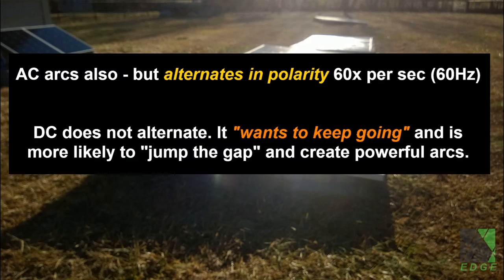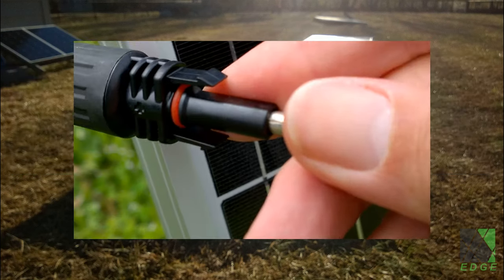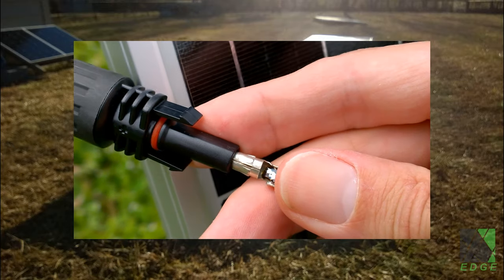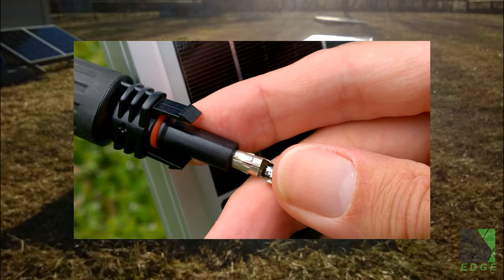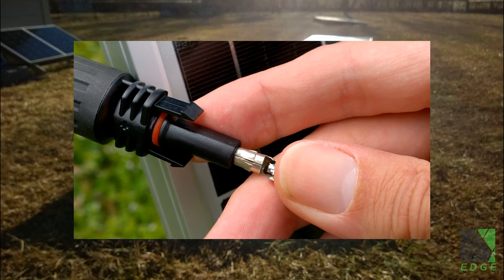Put in simpler terms, AC, or alternating current, can arc, but it alternates in polarity 60 times per second, or 60 hertz. DC does not alternate. It wants to keep going and is more likely to jump the gap and creates powerful arcs. By the way, many solar MC4 connectors have a notice on them that says do not disconnect under load. The reason for that is arcing.